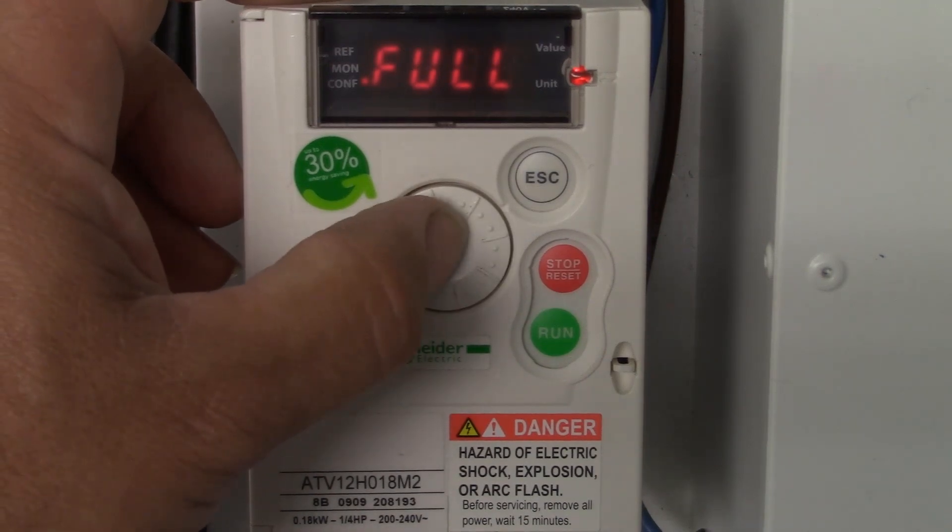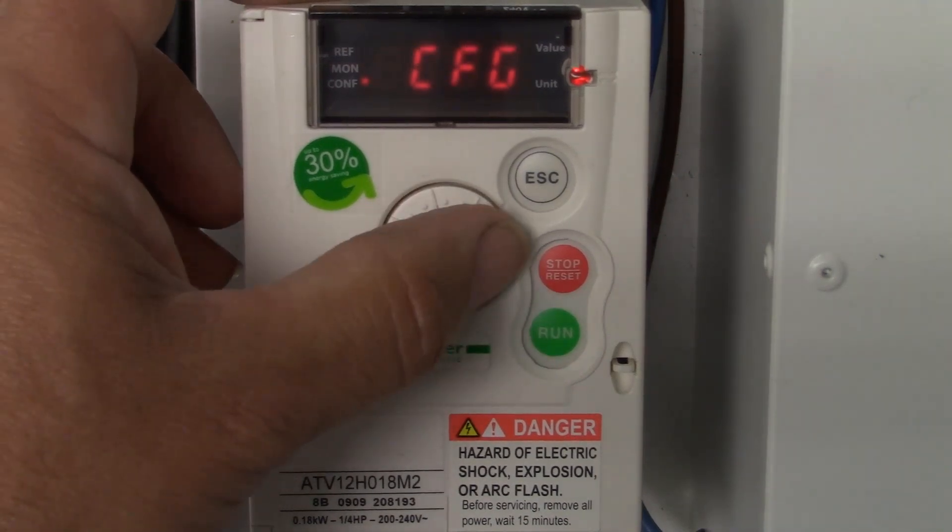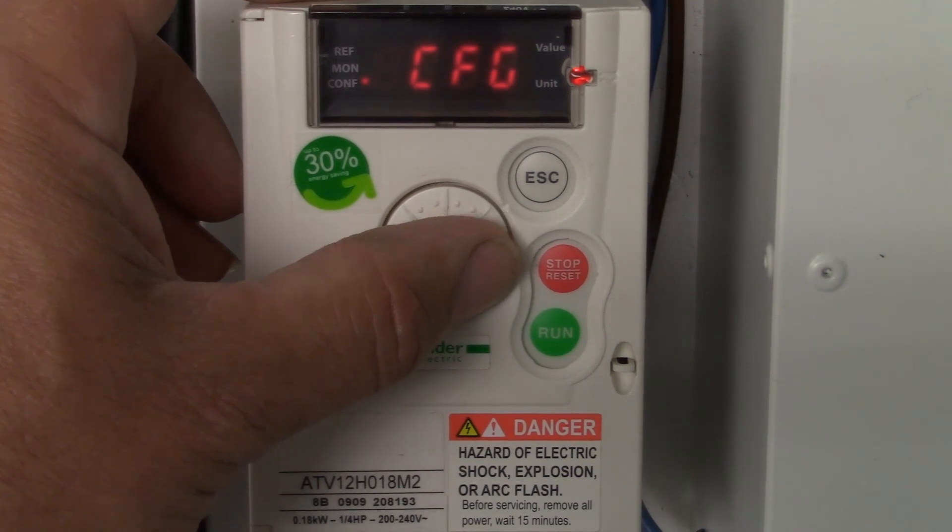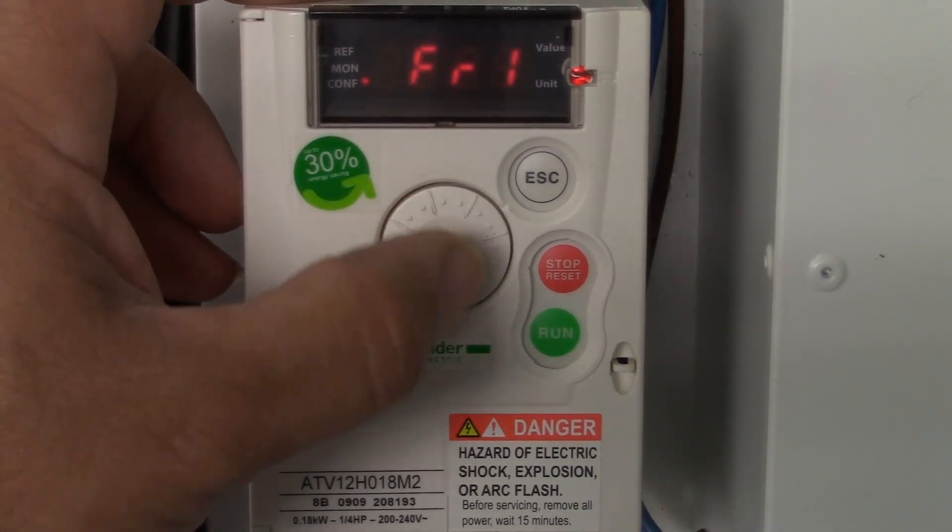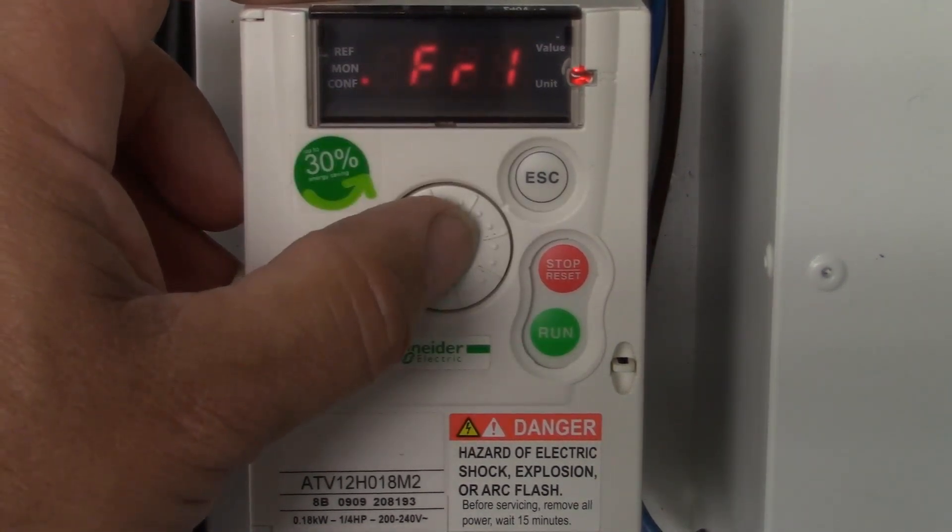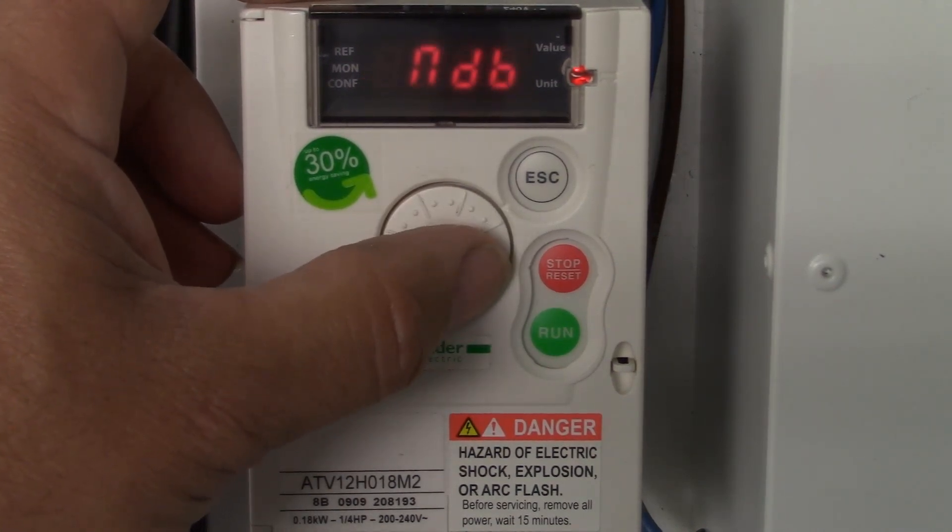First off we go to the config menu, then the full menu, then scroll down to the CTL and change FR1 to a different setting other than AI1. I am going to use the AIU1 for this example using the dial for reference.